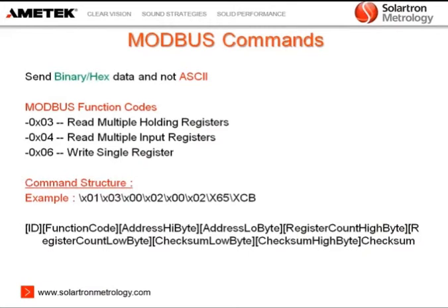And at the bottom, you have a command structure. I won't try to explain this example fully, but I'll just look at the first part. The first part, 01, is the ID of your MODIM on the Modbus network. So that's your MODIM number 1. And 03 is your sensor reading using the Modbus command, and then 02 is the location of the sensor, the network address of the sensor.